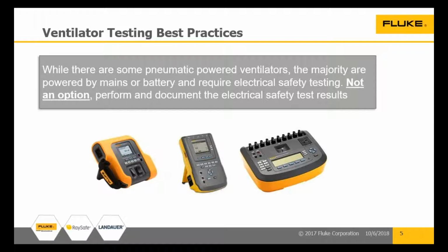Those two times. What about if you send a medical device out for testing and it comes back in? What event happens then? Another incoming inspection. Yeah, so it's not just when it's brand new, it's whenever it comes back. So you need to understand that. I want to make sure you clearly understand that. Document the measurements. For every other inspection outside of that, it's a visual inspection of the key things that fail for electrical safety, but no measurement.